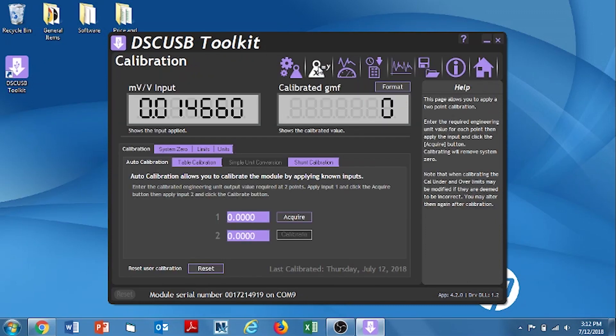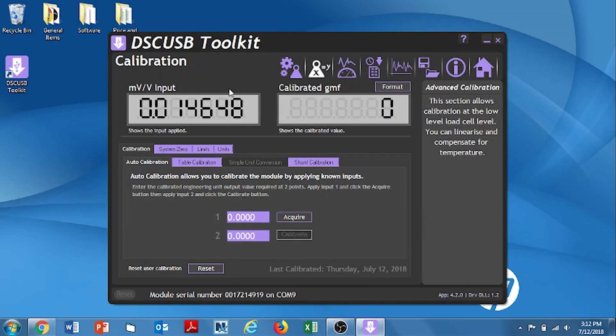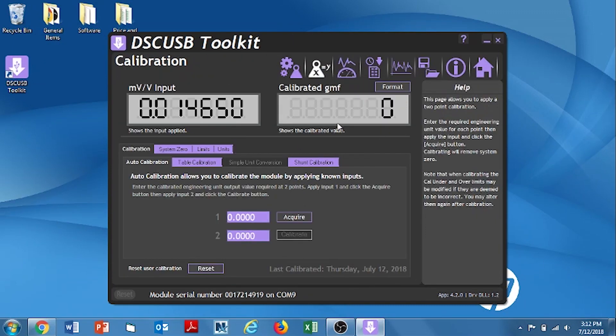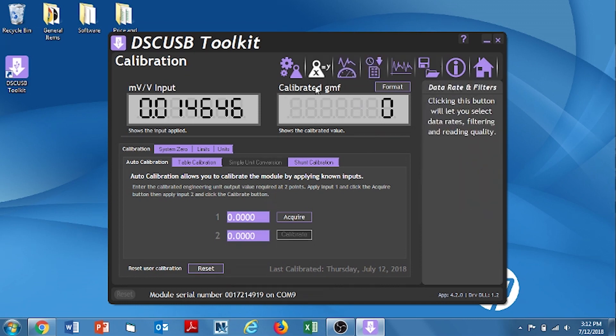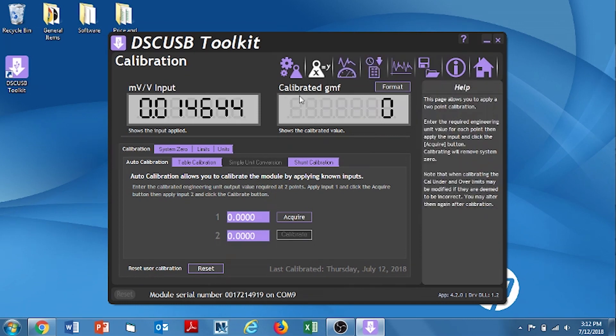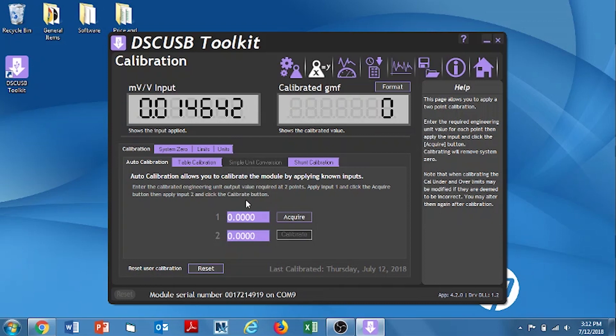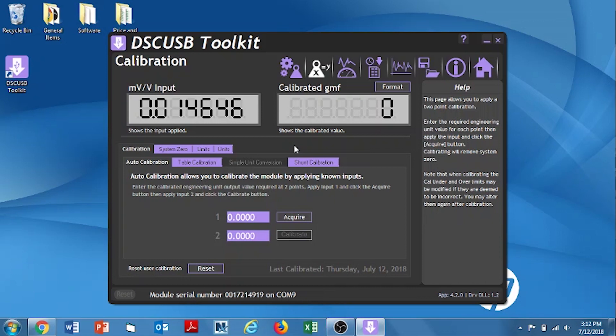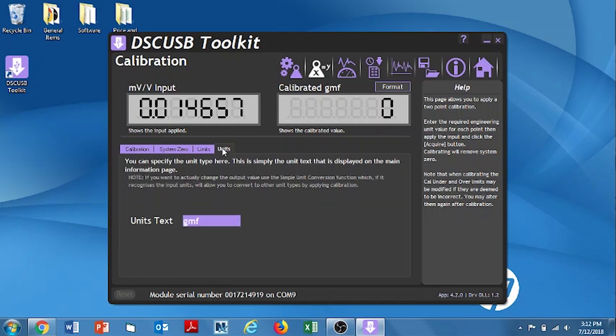And click the button. Now we're into this menu. And it's showing on one side the millivolt per volt input. That's coming from our load cell. On the right side here, it's showing the last calibration it had, which was in this case calibrated in grams force. For this particular calibration, we're going to calibrate it in pounds force. So, we're going to first go in and change the unit. And we're going to change that to pounds force. So, we click on the units tab. And change this by clicking on the gram force. And putting in LBF pounds force. Click OK.